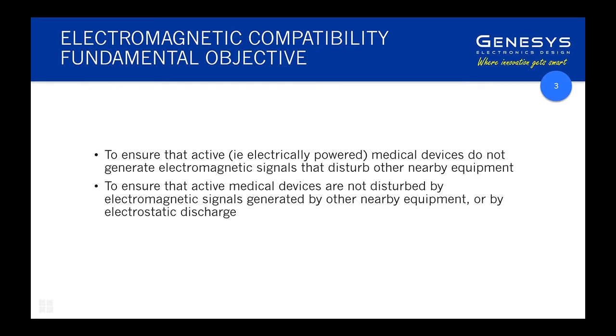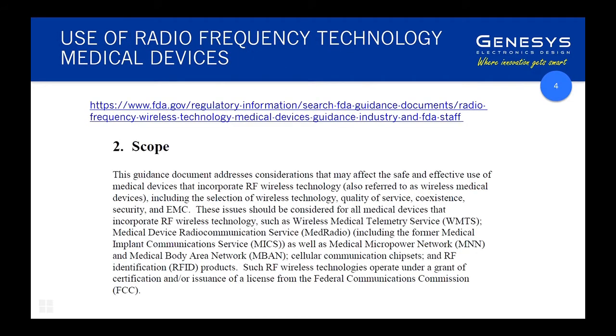The fundamental objective is that electronic and electrical devices can coexist in the environment without interfering with each other's operation. Electrostatic discharge is also included — that's a slightly different form of interference. Electric zaps are particularly problematic for electronic devices and can cause microcontrollers to reset or even cause physical damage.